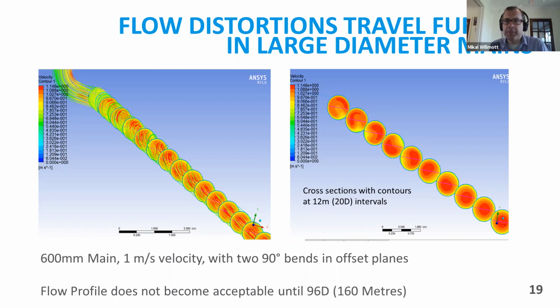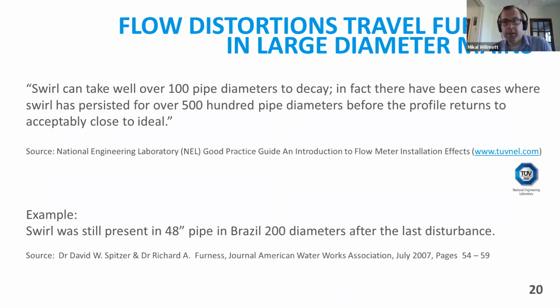And this distorted flow, or this disturbed flow, is dissipated. In a larger pipe, any single molecule of water takes a longer time to hit one pipe wall before it hits another pipe wall and then hits the other pipe wall again. And so this is why we think these distortions go on longer. So in this example, in this computer simulation, it's about 96 diameters, or 160 meters, before we get what we call an acceptable profile. Can we just go on to the next slide, please, Andy?